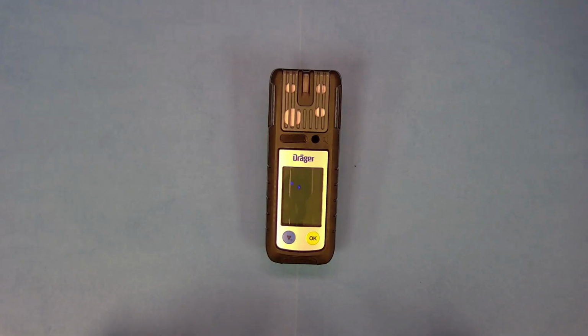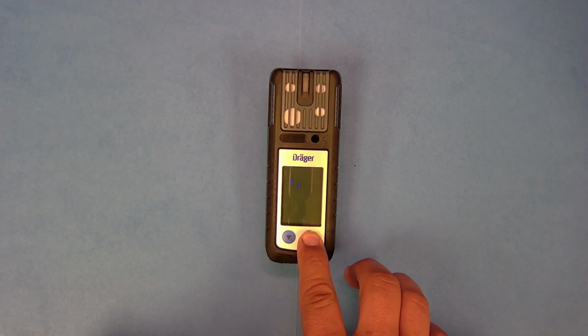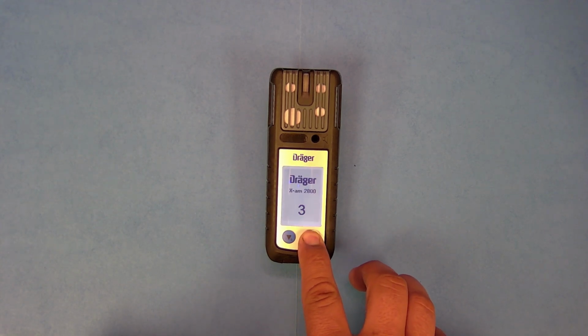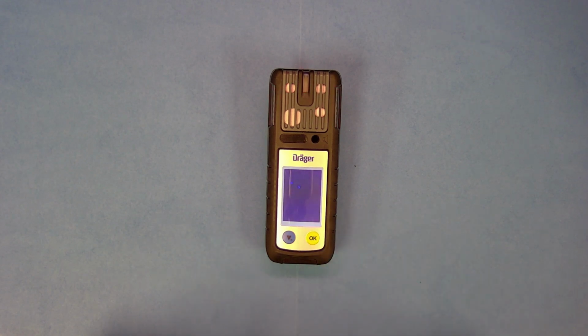To turn on the unit, hold down on the green OK button for approximately 3 seconds. The monitor will briefly alarm, then display various information as the monitor warms up. If you have multiple monitors for bump testing, the process can be accelerated if you start them all up before proceeding to the bump test or calibration procedure, whether done manually in the bump test station or preferably on the X-Dock docking station.